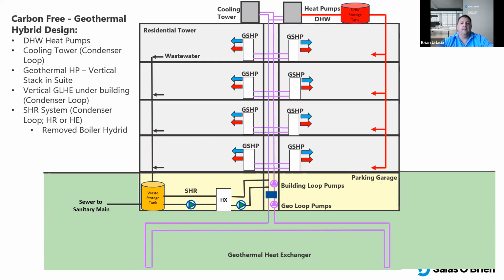So we really have to look at, when we go all electric, what is that peak going to look like? How are we peak shaving? Are we using any hybrid equipment? One thing you can also add is thermal storage - if you're getting close to that peak on the electrical side, we can put in thermal storage to reduce that capacity and continue to heat and cool the building even while running at part load condition. By marrying all these technologies together, we absolutely can electrify these buildings.